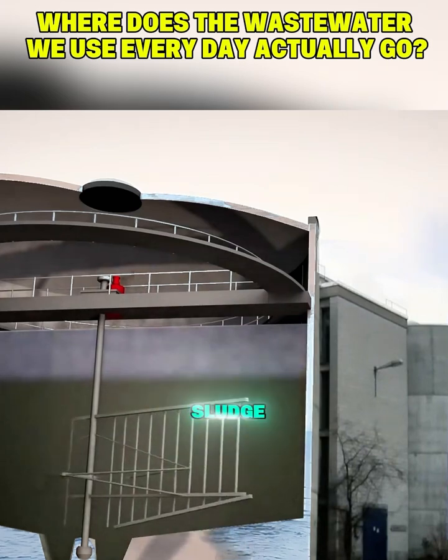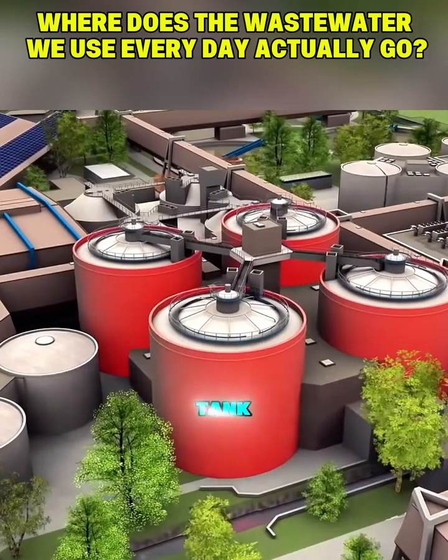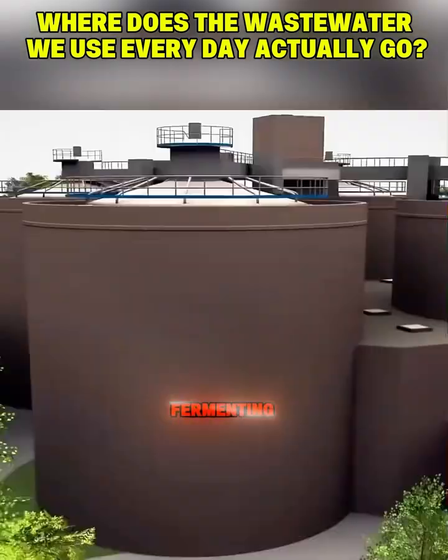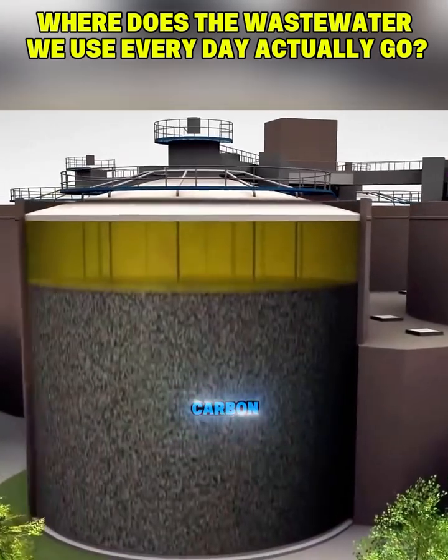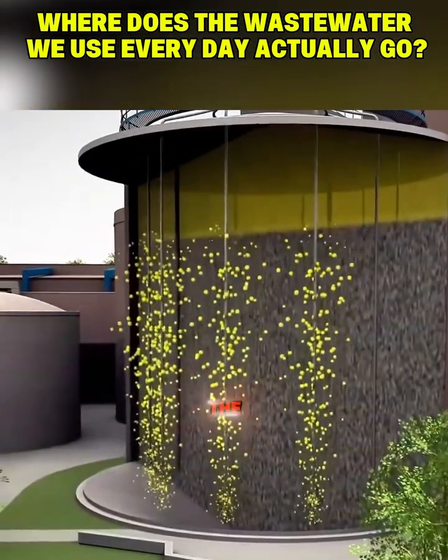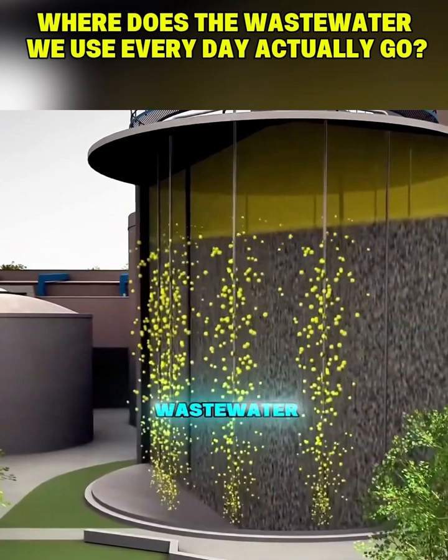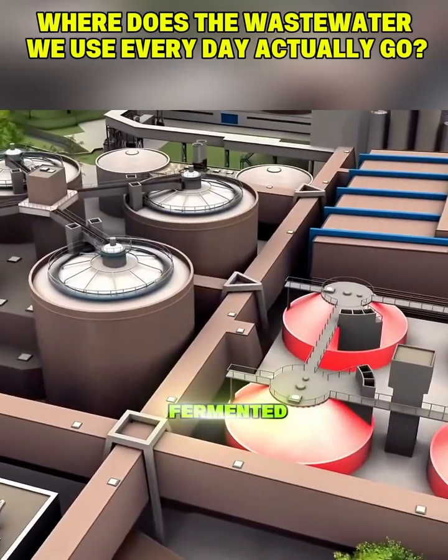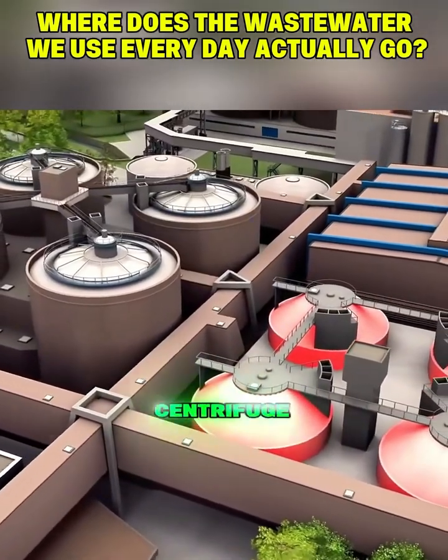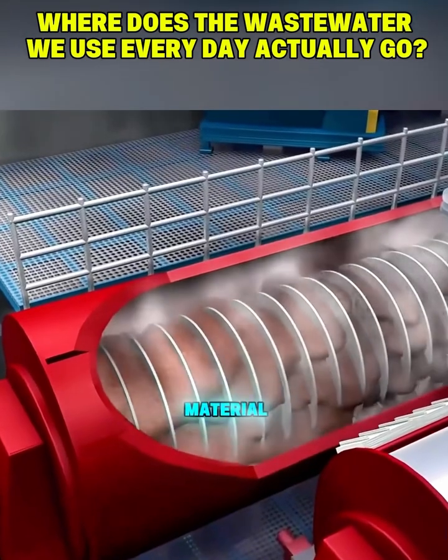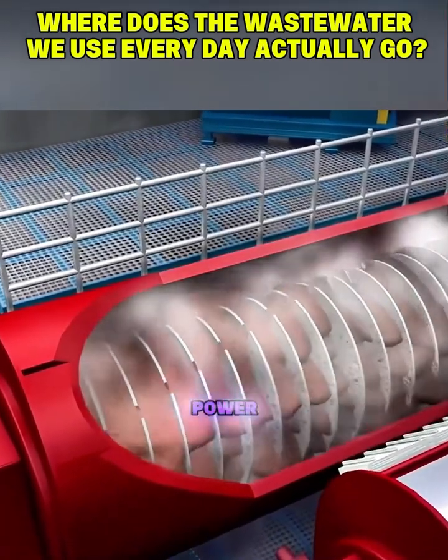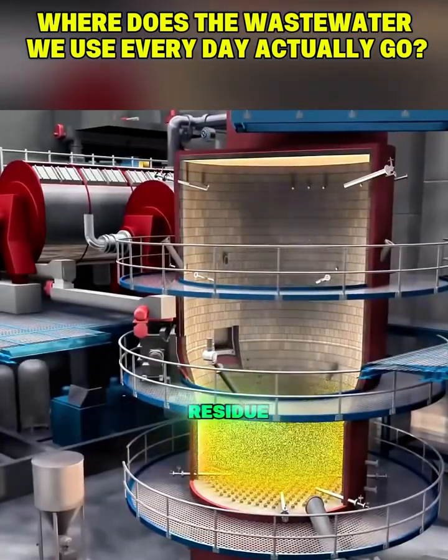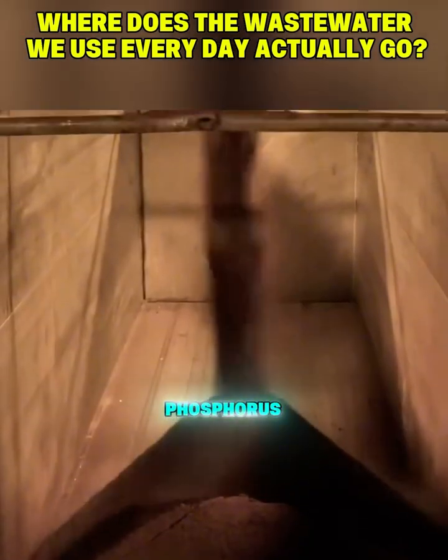The remaining sludge is sent to a fermentation tank, where it is heated to continue fermenting, producing methane, carbon dioxide, and water. The methane gas can be used to heat the wastewater treatment plant. The fermented sludge is dewatered using a centrifuge. The resulting solid material can be incinerated for power generation. The combustion residue, which contains phosphorus, can also be used as organic fertilizer.